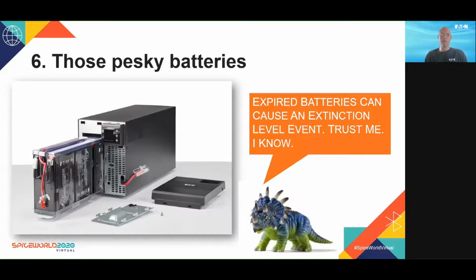So let's talk about those pesky batteries. So battery replacement averages anywhere between 3 to 5 years for VRLA or lead acid. So keep a record of when batteries were replaced. Replace all batteries at once, including both internal and external batteries. Batteries kept in storage without periodic charging will die. An effective UPS battery maintenance program must include regular inspections, adjustments, and testing with thorough records kept.